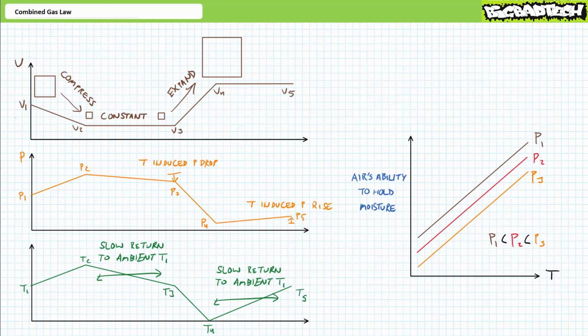As you're probably aware, only in very rare occasions do such isolated single property changes occur. During a rapid adiabatic compression, one might move from curve P1 to P3, at the same time moving slightly right along the temperature axis, to find condensation forming in the reservoir. Steps need to be taken to rid the system of this accumulated moisture, either through routine draining of the receiver or the use of supplementary equipment like dryers.